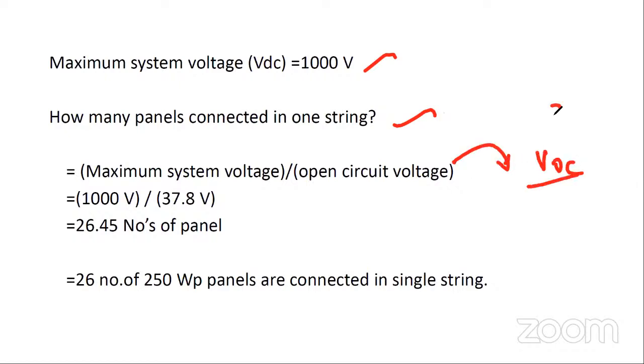For the 250 watt panel, we have seen the VOC is 37.8 volt, but the maximum VDC given is 1000 volt. If you divide 1000 volt by 37.8, it gives 26.45, so 26 panels can be connected in series in one string in order to not exceed 1000 volt. We drop the decimal, so 26 panels of 250 watts can be connected in one string.